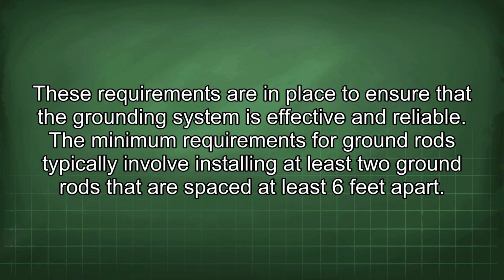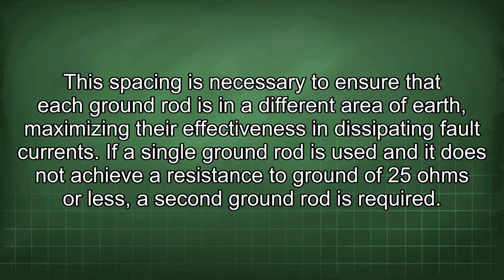The minimum requirements for ground rods typically involve installing at least 2 ground rods that are spaced at least 6 feet apart. This spacing is necessary to ensure that each ground rod is in a different area of earth, maximizing their effectiveness in dissipating fault currents.